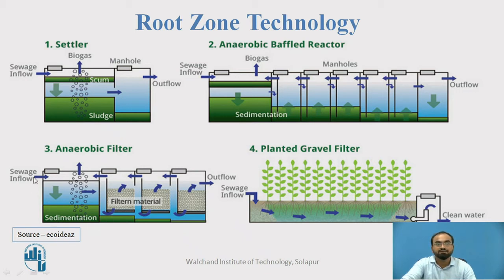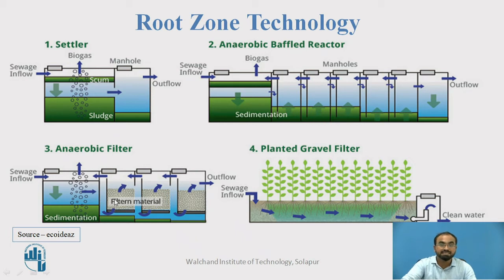In the anaerobic filter, first anaerobic digestion is provided — as in the settler and anaerobic baffled reactor — and then a large amount of filter media is provided. Water is pushed from the bottom upward, where any remaining suspended particles are trapped and removed. The clearer water then passes through the next filter media and similarly through a third filter media, so three filter media are provided in series.